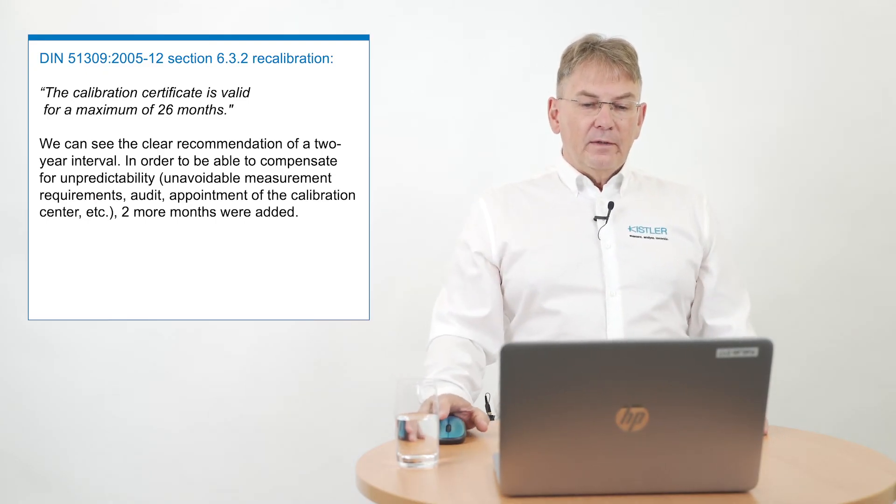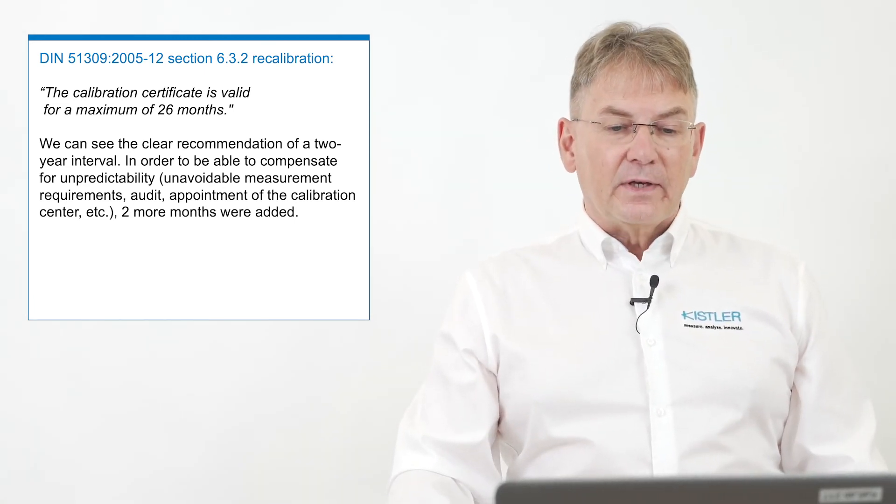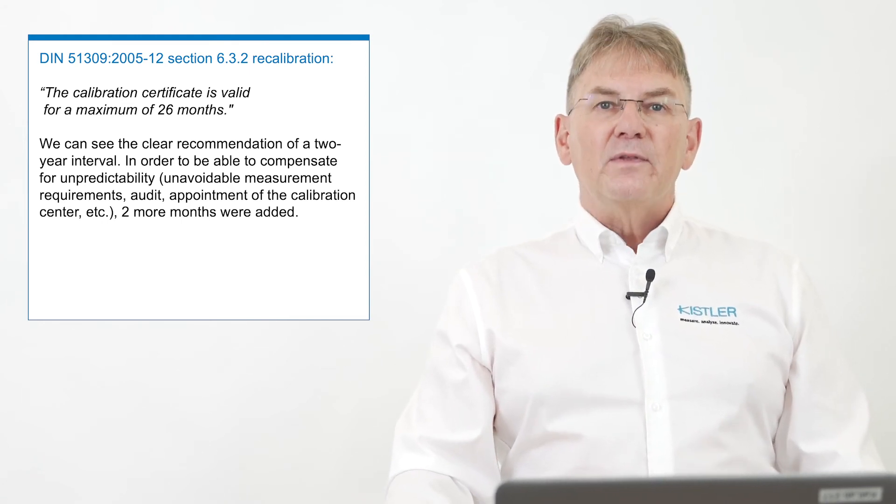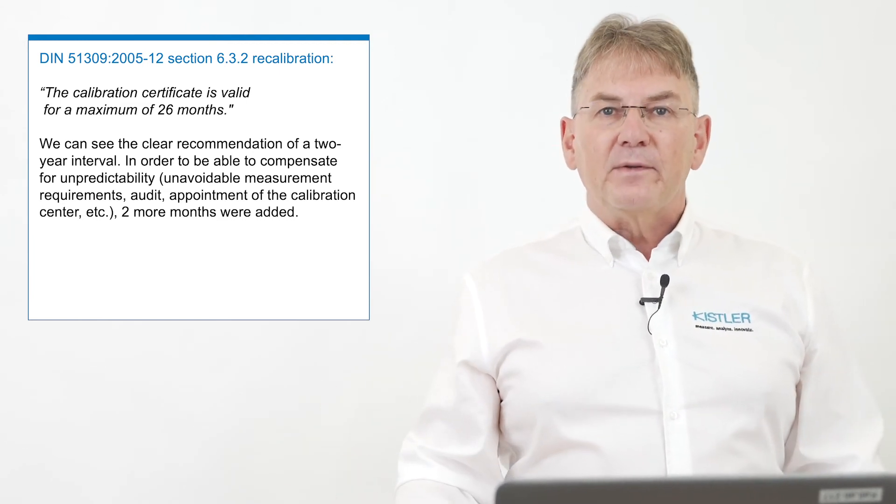People writing norms found out that some customers choose those extreme long intervals of 6 or 8 years. As mentioned before, that doesn't make sense. So what they did is they limited the validity of calibration certificates — not the calibration intervals, but the validity of calibration certificates. Up to 26 months is a very common limit: 24 months plus 2 months for shipping and handling. You as the instrument holder are still responsible for the calibration intervals, but these norm writers limit the certificates. For example, DIN 51309 in section 6.3.2 on recalibration states that the calibration certificate is valid for a maximum of 26 months — forcing customers to a good interval of about 24 months.